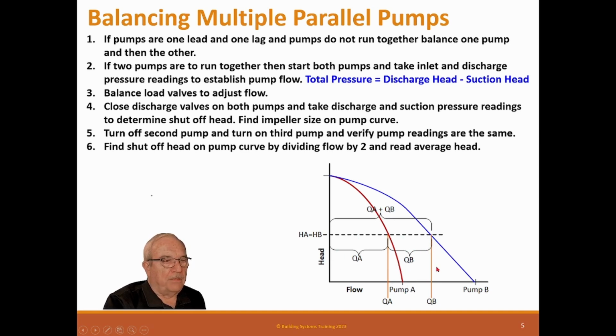So the second pump doesn't add 50% of flow. And that's where some engineers will mess this up and think that with two pumps you get twice the flow of each pump, and you do not. It is going to be about 10 to 15% less. You add a third pump, it'll be 20 to 25% less. You add a fourth pump, it'll be 40% less. So it gets less and less flow as you go. That's why we only see three pumps.